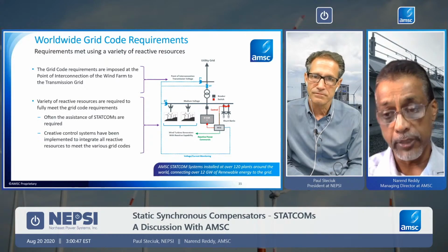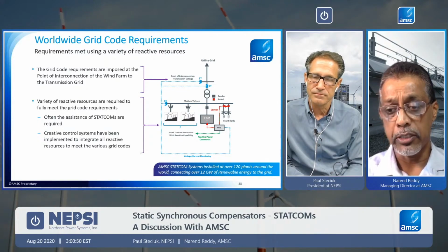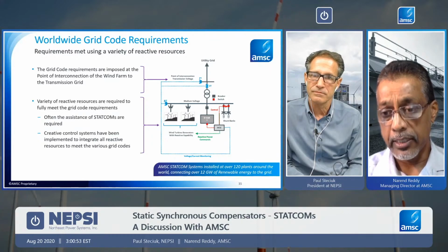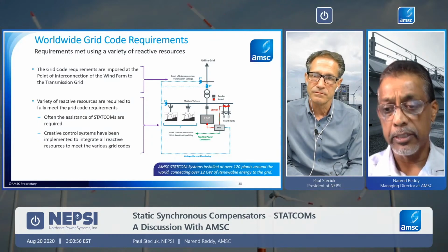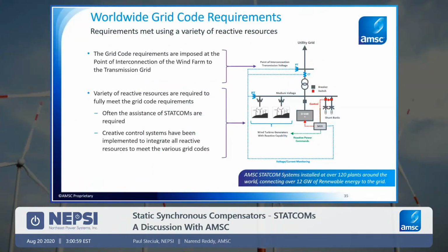really right at the point of connection, typically at the substation collector bus, where all of that power is stepped up to the transmission point of interconnection. That's really the ideal location to fill in any gaps in terms of the performance of the wind plant overall. And that's what helps us actually configure and sell a lot of this, because the DVAR can, at that point, really take on the role of a master controller for the wind plant, while the turbines are focused on the megawatt generation and making sure that they are optimized to put out as much megawatt as the wind is blowing and can be harnessed.